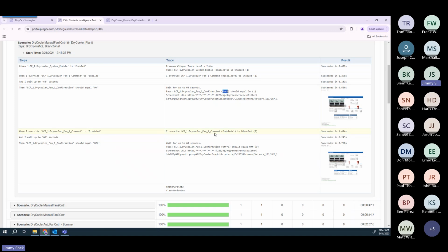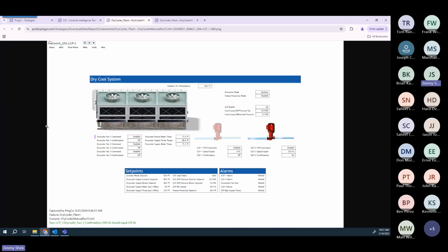So again, on the trace, you'll see that the fan is currently enabled. Now we're doing a BACnet override to disable it, waiting up to 60 seconds, and then checking that confirmation. And then you'll see here, this is kind of the equivalent screenshot. So now you'll see that the fan1 command is now overridden to be disabled, and we lost confirmation as expected.